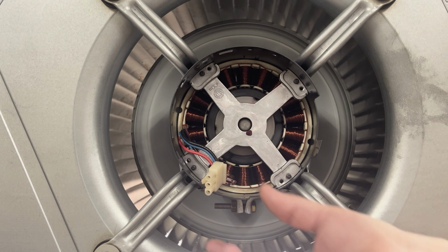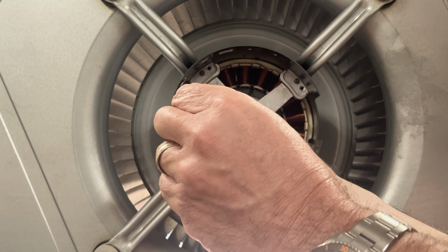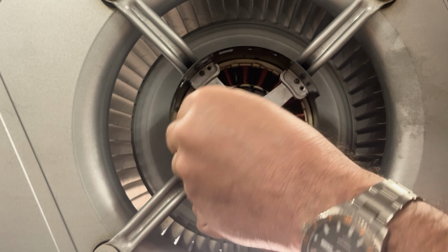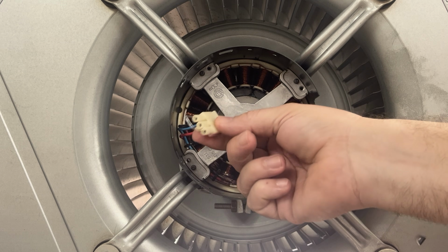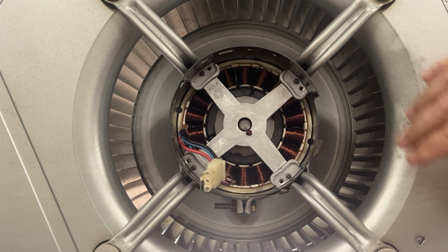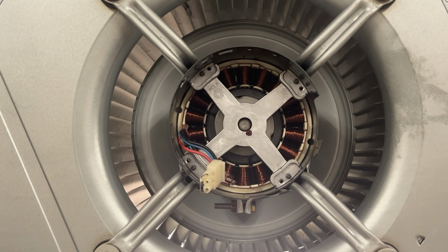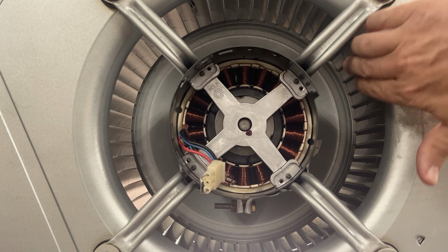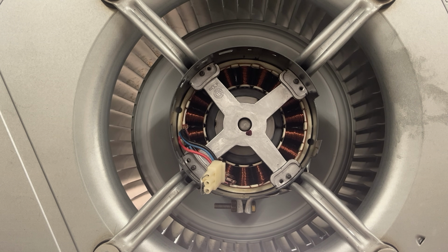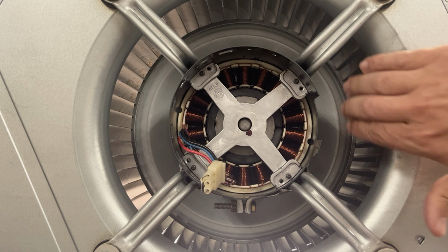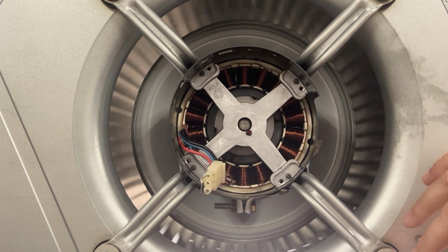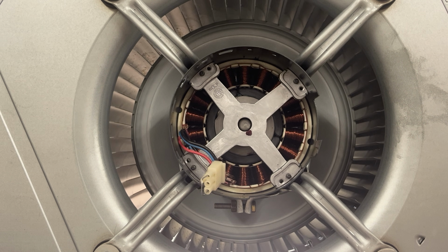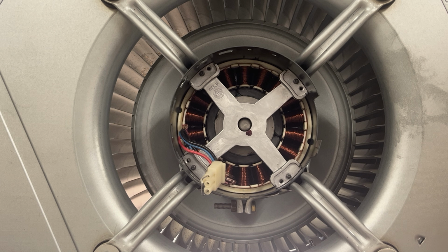And so if I were to see if I had a bad winding on this motor, I would simply connect my paper clip in there like that to short out those two windings. I'm gonna try to spin it again. As you can see here, it stops. That's why we call it the brake test. And so if you have resistance on this motor, you can have that resistance and have bad winding.